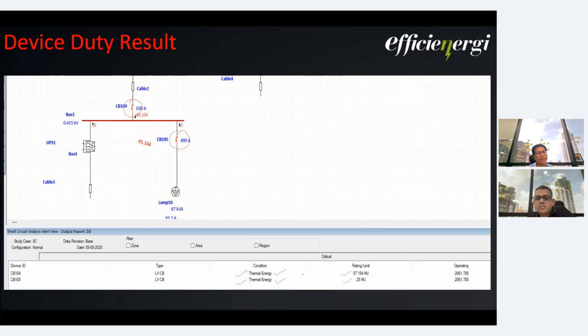So here in these two breakers, if you see the capacity, I will go to the next slide. The capacity and the fault current here is 45 kiloampere, but still it is showing failed. Now these breakers are 50 kiloampere rated. So I'll show you the next slide.